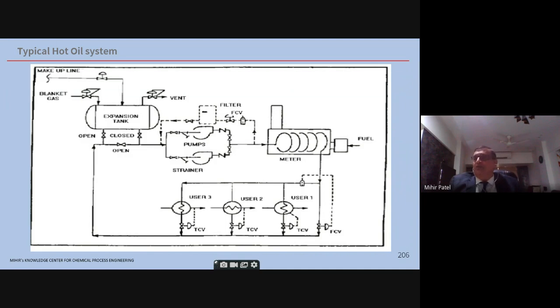The expansion tank is kept because you may want to heat up the hot oil from ambient temperature. Let's say you have a Diwali shutdown of 10 days. Your hot oil has cooled to 40 degrees. You want to now heat it back to 300 or 290 degrees. The thermal expansion is a huge quantum. That's why the expansion tank is kept.